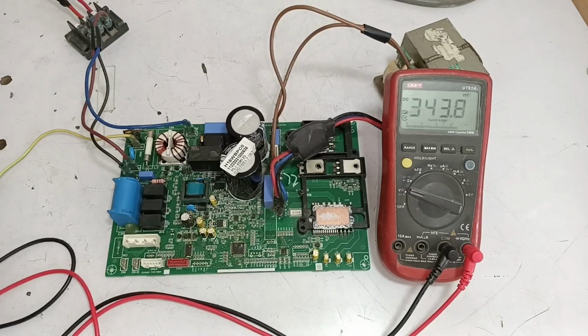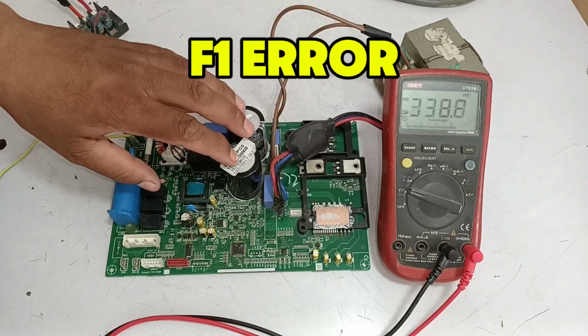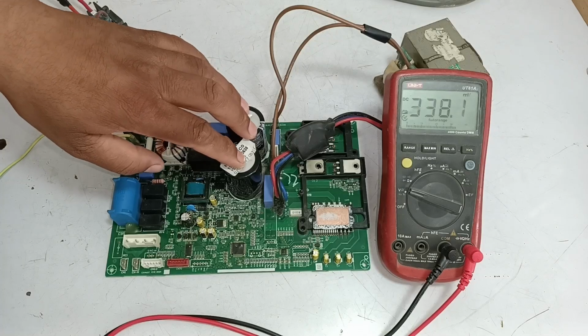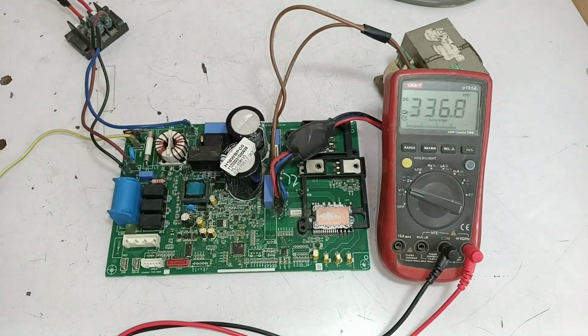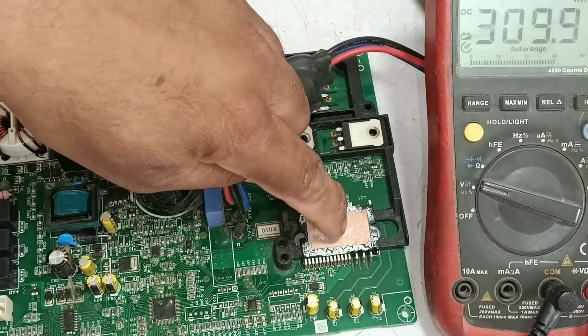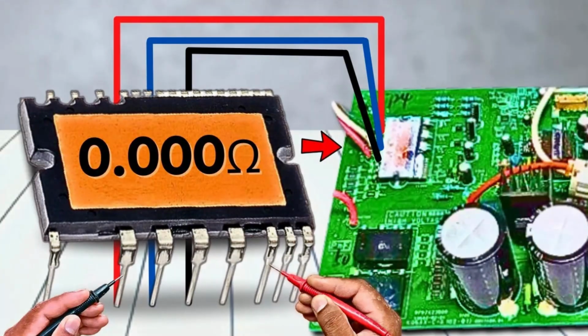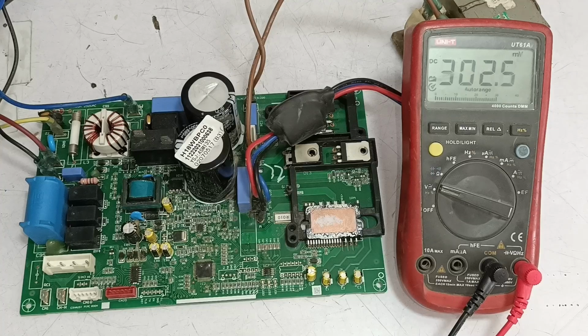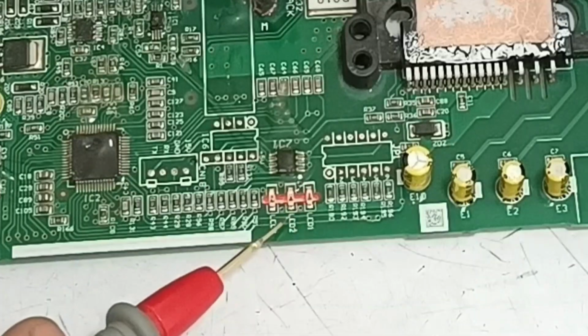This mini-split air conditioner circuit board is showing an F1 error code. Let me explain the main problem that the company has mentioned. According to the company, this error occurs due to the IPM, and I have already made a video on how to test the IPM. The LED light is turning on very late after it's powered on, and here you go, the LED is turned on.